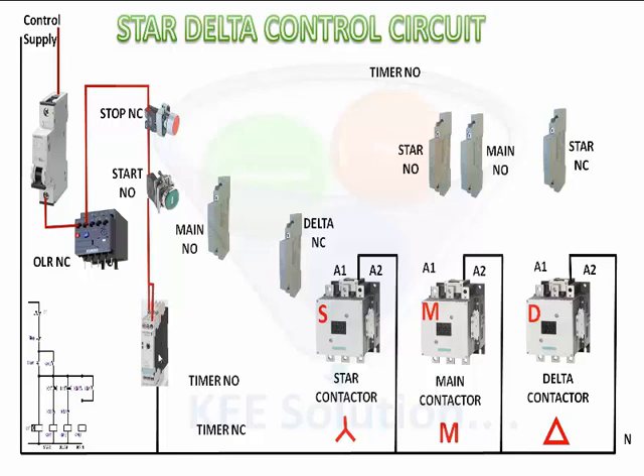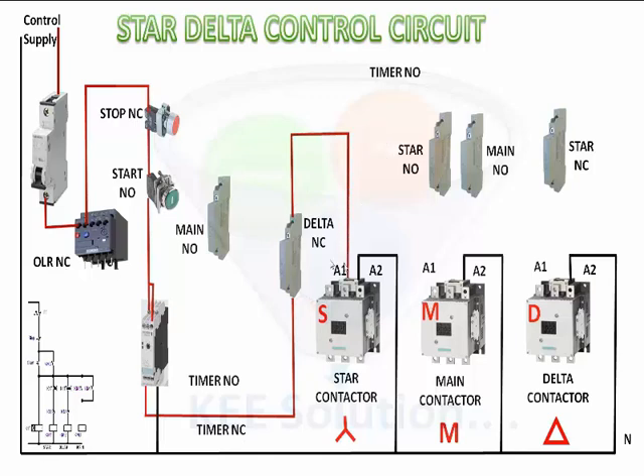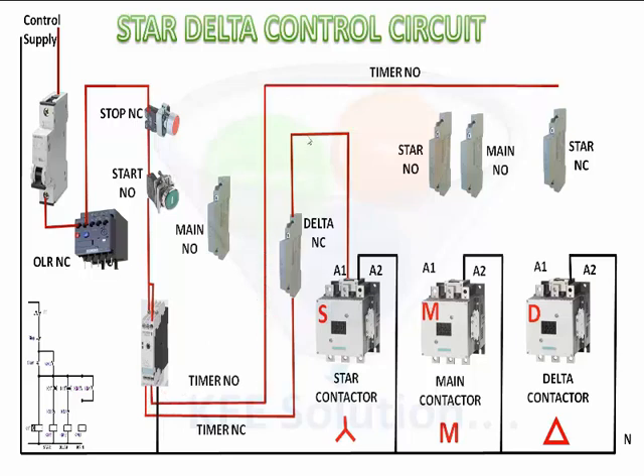We take timer NC, which goes to the delta NC auxiliary contact, and then connects to A1 coil side of the star contactor. Timer NO side connection will go to the star auxiliary contact NC and terminate at the delta contactor coil at A1 side.